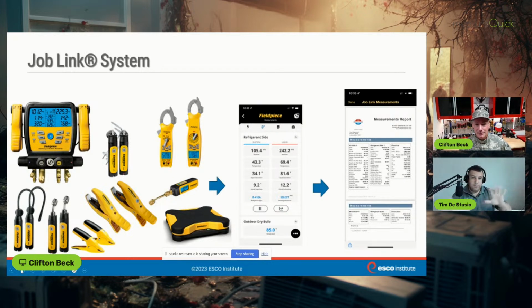Exactly, and as those variables are different, you come back in the springtime, it's not hot anymore, it checks the performance against that benchmark with those variables built in. So using Measure Quick, I'll tell you as a contractor, you will not succeed in the next generation of heat pump installations if you are not using Measure Quick as intended. Your root of failure will come back to not properly commissioning and checking a system, and it doesn't have to be that difficult anymore.